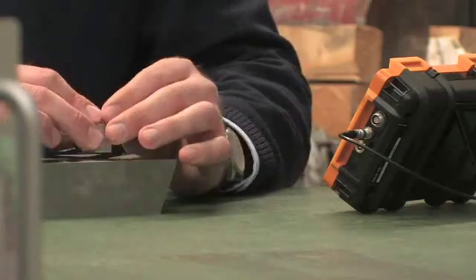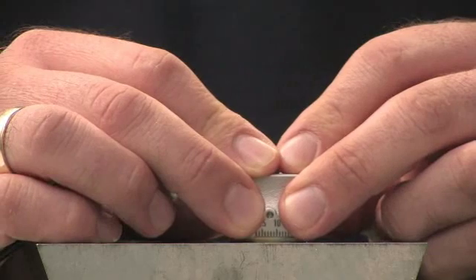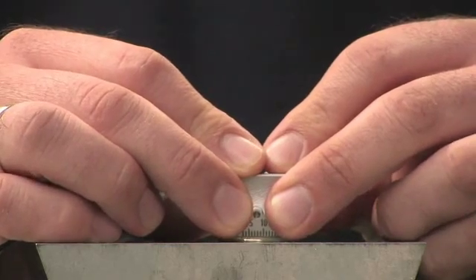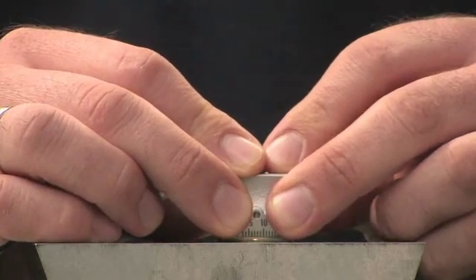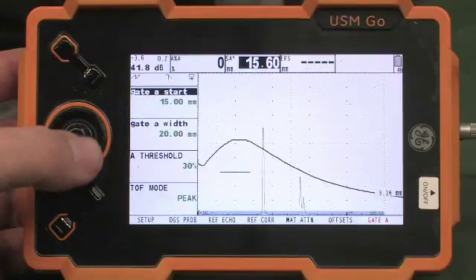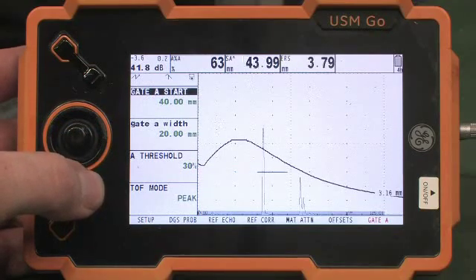The only remaining actions are to choose the equivalent reflector size and to switch on the DGS mode. After a flaw indication is found, the gate has to be positioned over this signal. The equivalent reflector size is then automatically evaluated and displayed by the instrument.